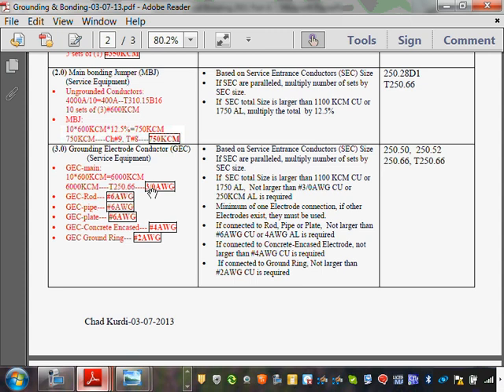So now we size the grounding electrode conductor for a 4,000 amp switchgear. Yes, sir. I have a scenario. What if they ran the conduit, these parallel sets, in PVC? Nothing will change. And they bring just one ground over rather than paralleling it.